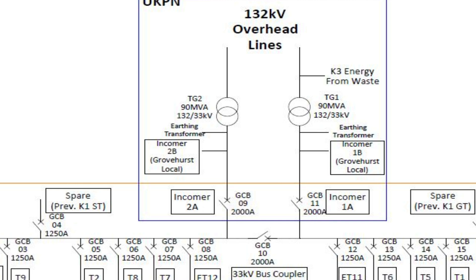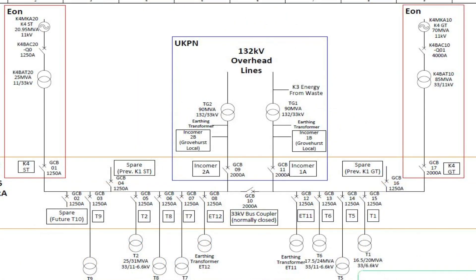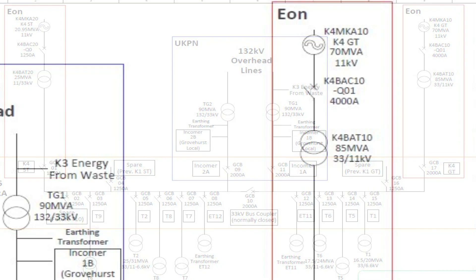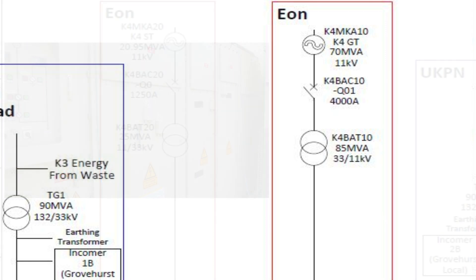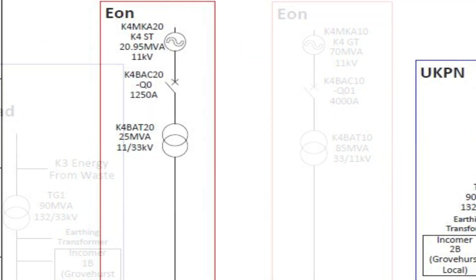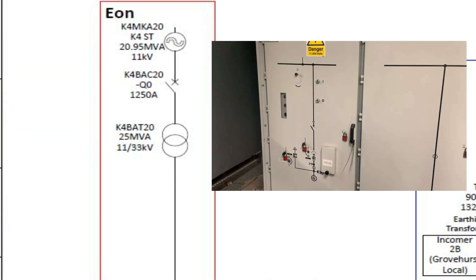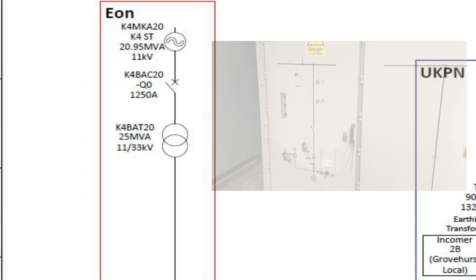If only one side incomer is opened but the bus coupler is closed, then the generator associated with that side of the board has to be opened. This is achieved at the 11kV level with the opening of the generator circuit breakers K4BAC10 for the GT or K4BAC20 for the steam turbine.